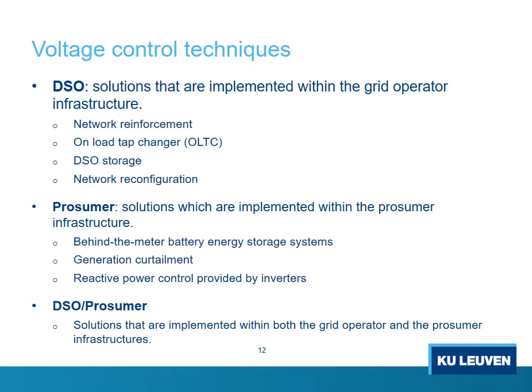Photovoltaic inverters and photovoltaic battery inverters can participate in voltage control by expanding their features with added grid voltage support functions, without major hardware modifications. These functions allow them to absorb reactive power to mitigate voltage rise, or inject reactive power to mitigate voltage drop. They can also curtail photovoltaic power to mitigate voltage rise, and charge the battery during the photovoltaic peak period to mitigate voltage rise, discharging it during the demand peak period to mitigate voltage drop.